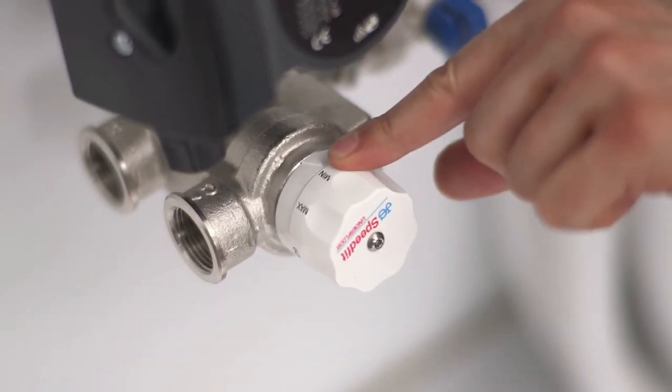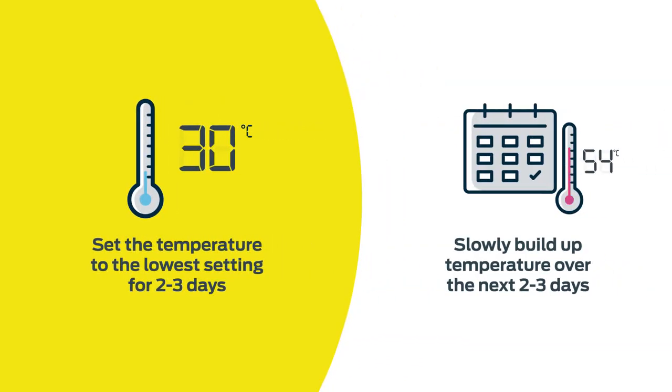When turning on initially, the temperature of the blending valve should be set to the lowest setting, 25-30 degrees, and run for 2-3 days before building up the temperature over the next couple of days.